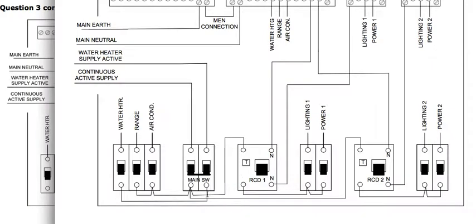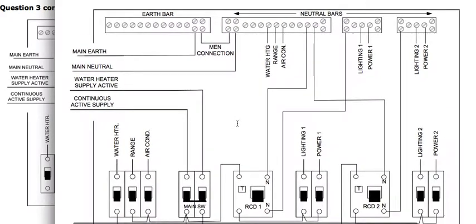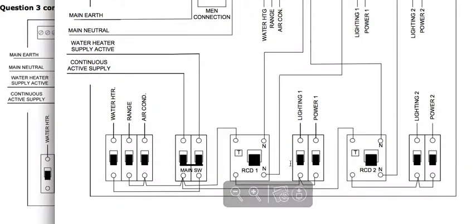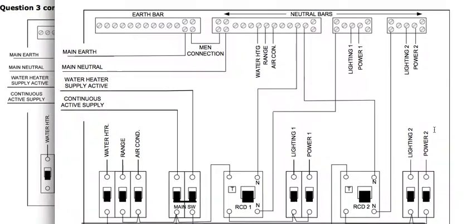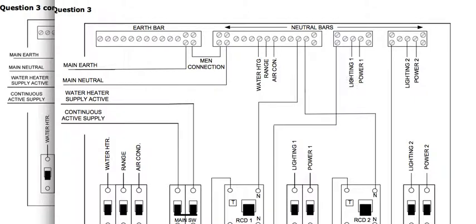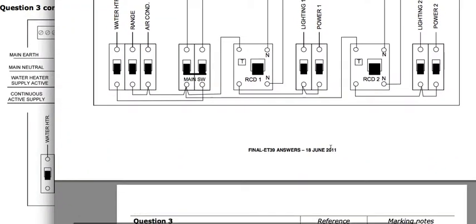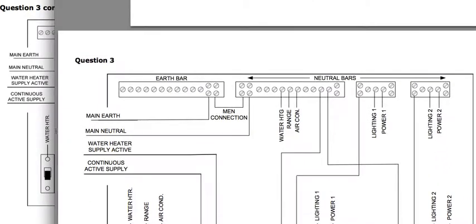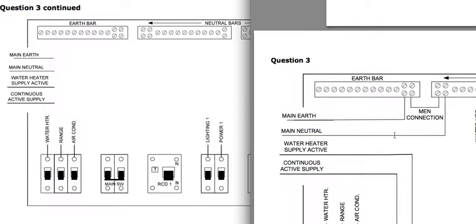So we've got an RCD1 that's got a neutral connection there, and that's feeding our lighting and power one. And we've got RCD2, which also gets its feed from the main switch, and that feeds lighting 2 and power 2. And we've got our neutrals connected lighting and power through our neutral bars, our separate neutral bars. So it does look quite a scary question, but I think if you keep to the basics of how you wire the switchboard, then you can't go far wrong.